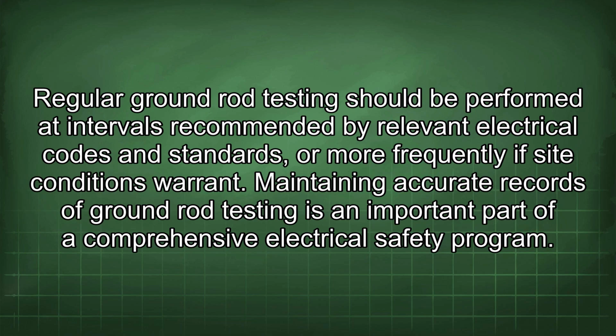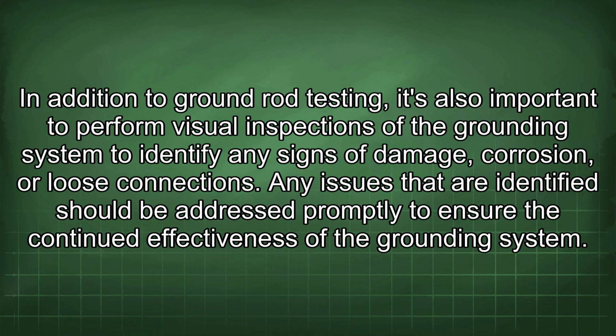Maintaining accurate records of ground rod testing is an important part of a comprehensive electrical safety program. In addition to ground rod testing, it's also important to perform visual inspections of the grounding system to identify any signs of damage, corrosion, or loose connections. Any issues that are identified should be addressed promptly to ensure the continued effectiveness of the grounding system.